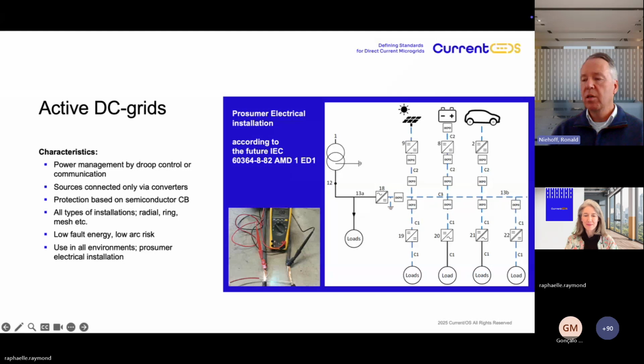The small picture in the middle shows what a short circuit does in an active DC application where semiconductor circuit breakers protect the wiring, and you can see that there is a very small arc occurring even when the cable is able to carry 700 volts, 70 kilowatts.